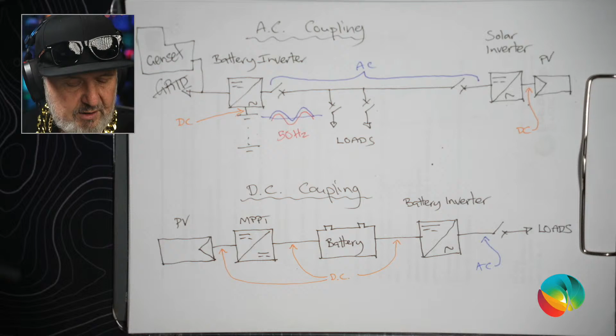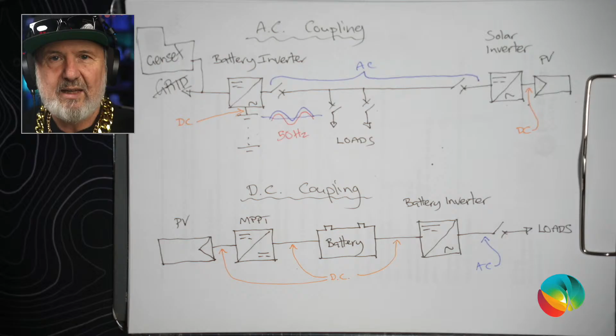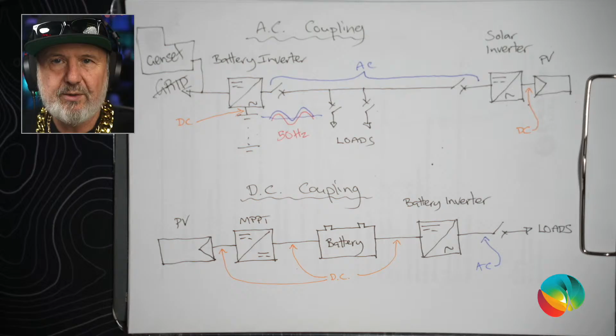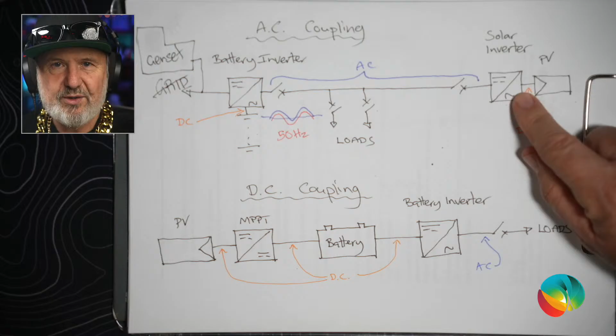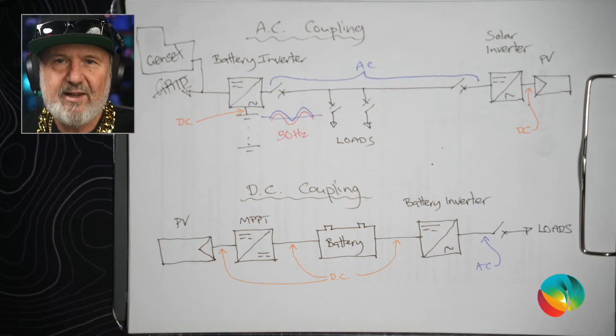There's what they call generic control, and generic control is actually using one of the features built into our grid protection standard, AS/NZS 4777 Part 2. AS/NZS 4777 Part 2 is the standard that inverters that can parallel with the grid must meet, and one of the mandatory features of that is that they have a power frequency response mode by default. And what that means is if the frequency of the grid rises, the power of the inverter must reduce. Now that gives the ability for the battery inverter, which after all is the grid forming inverter, to control the generation by very slightly changing the frequency.